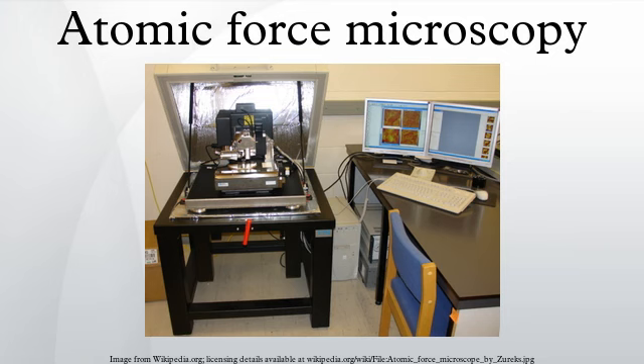Several types of interaction can be detected. Depending on the interaction under investigation, the surface of the tip of the AFM probe needs to be modified with a coating. Among the coatings used are gold, for covalent bonding of biological molecules and the detection of their interaction with a surface, diamond for increased wear resistance, and magnetic coatings for detecting the magnetic properties of the investigated surface. The surface of the cantilevers can also be modified. These coatings are mostly applied in order to increase the reflectance of the cantilever and to improve the deflection signal.